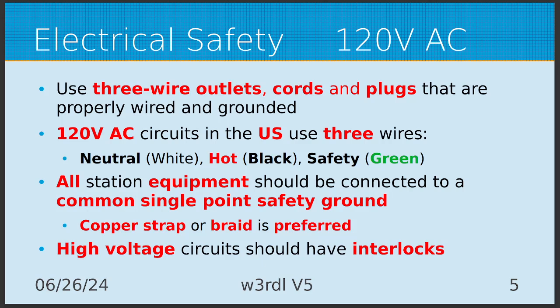Ground rods by Florida building codes are supposed to be 8 feet now. You might think it's easy to put 8 feet of 3/8 inch copper post into the ground because it's Florida sand — it should be nothing at all. Not the case. Sometimes you have to work on it a little, maybe change the location.